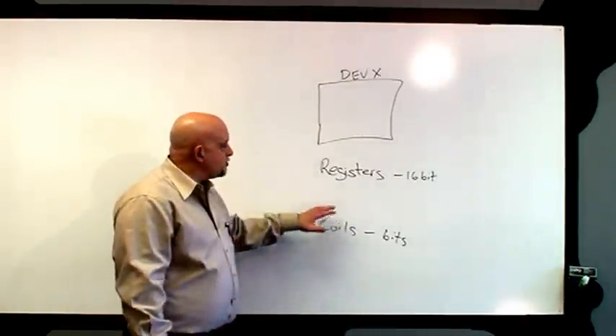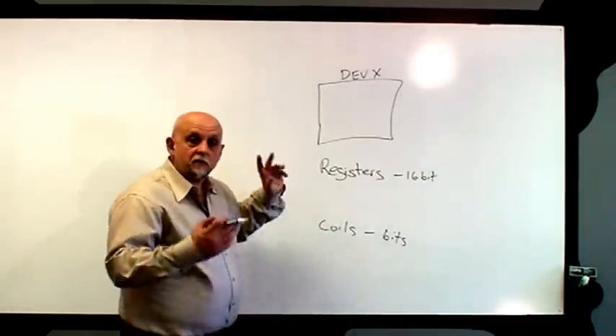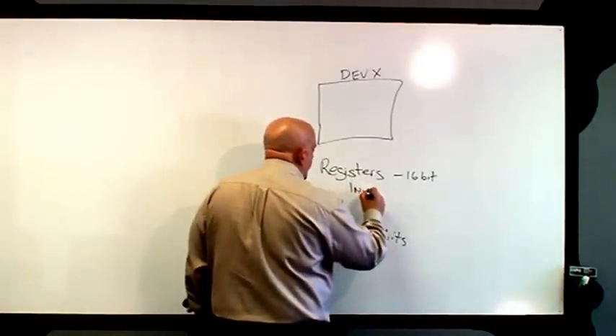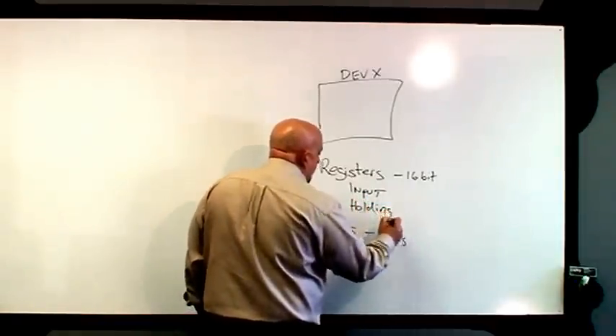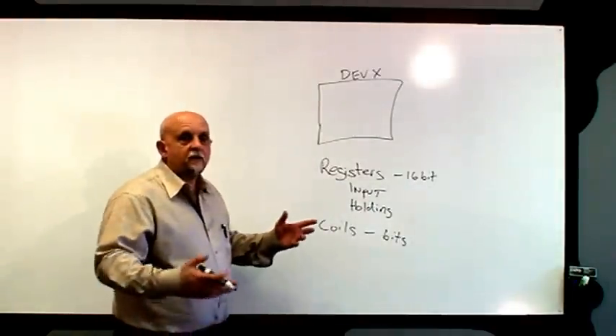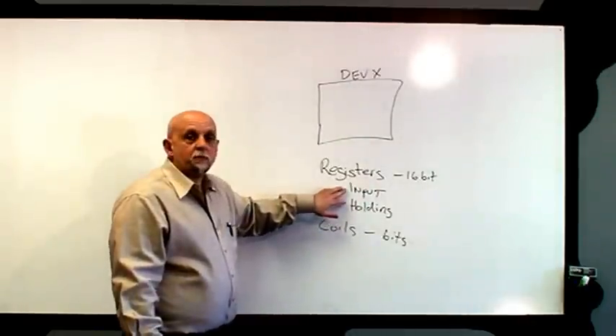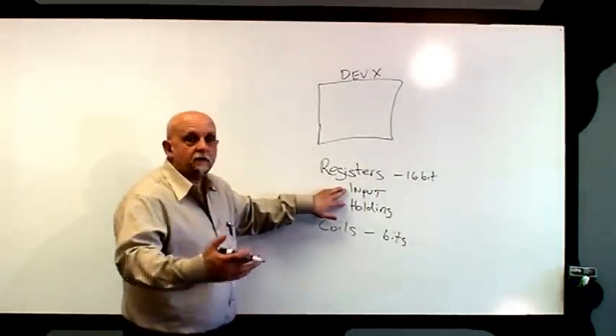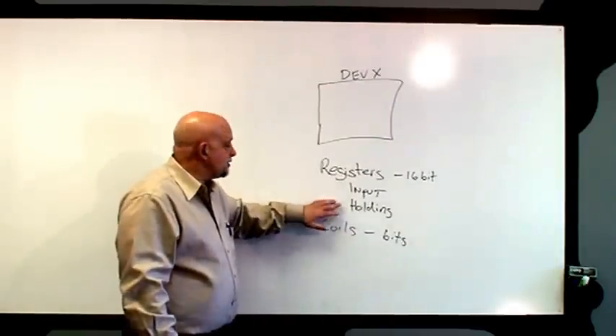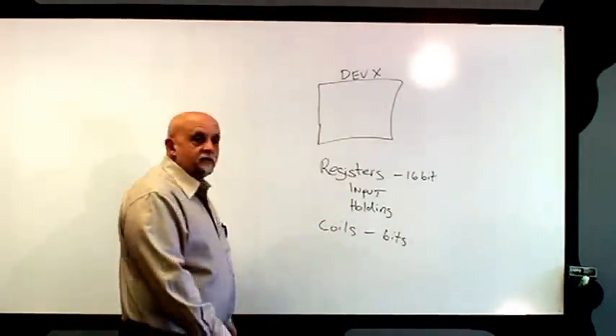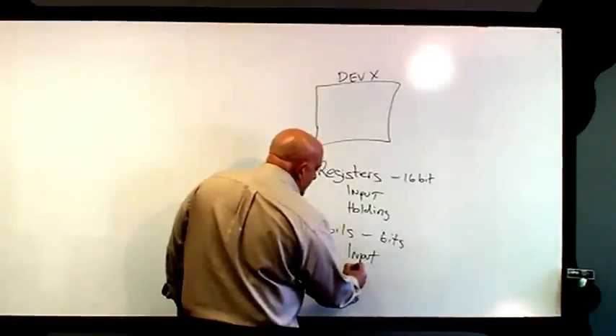The manufacturer has the choice of deciding what kind of registers they are, and there are basically two kinds: input and holding. Input registers are places to hold data coming in from the field. Holding registers, as the name says, hold data being used in the logic process. You have the same thing with coils — you have input coils and status coils.